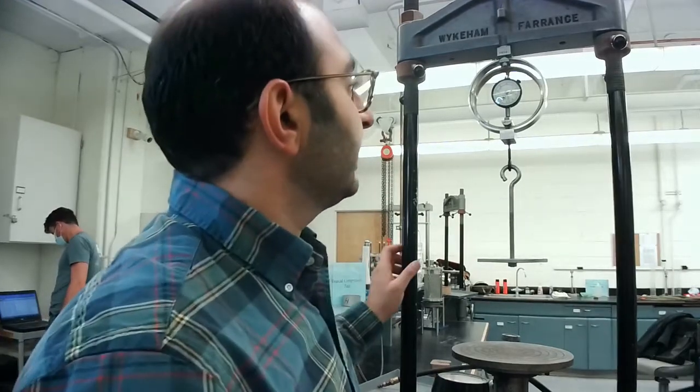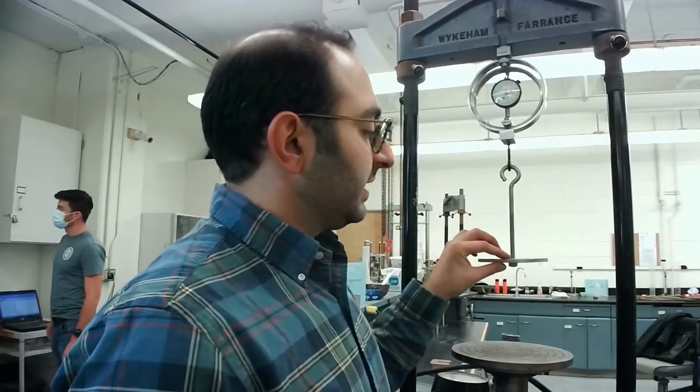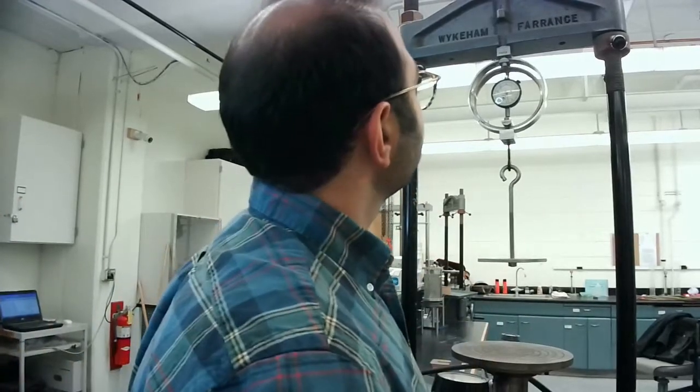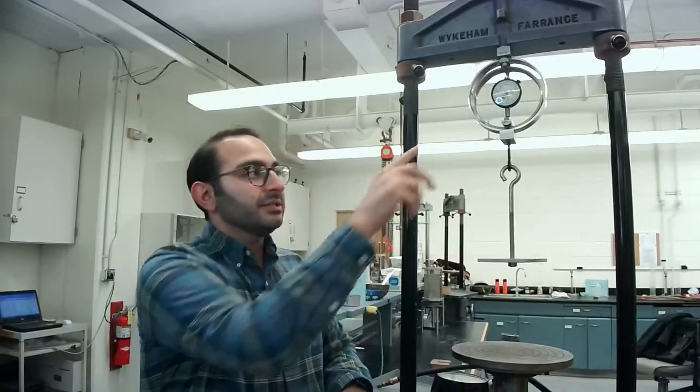I started off at six hundred and fifty-one with the hanger on, and now by loading and unloading I am at six hundred and forty-seven. So this was the process to calibrate the triaxial load ring.